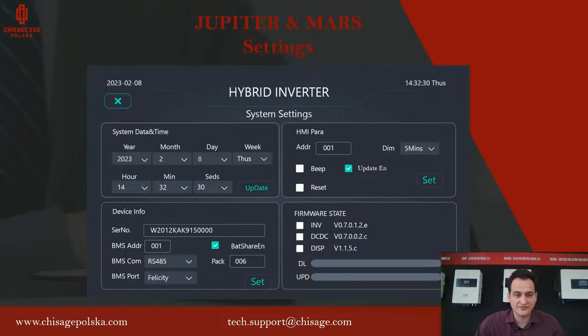For our batteries, if you have our batteries, you will use the Pylon Tech protocol, so you pick Pylon. So for our batteries, it will be 001 RS485 and Pylon, or 000 CAN and Pylon. That's for our batteries. Battery share enable is for parallel connection. It's information for the inverter that it's not the only inverter charging the battery. So if we parallel inverters and parallel batteries, the inverter will know that it's not the only one charging this battery. And for battery packs, we put how many battery packs we have.